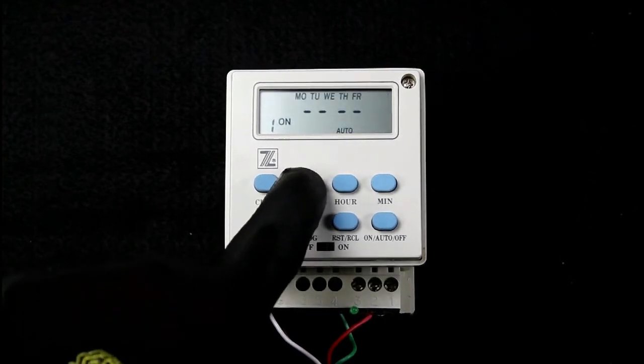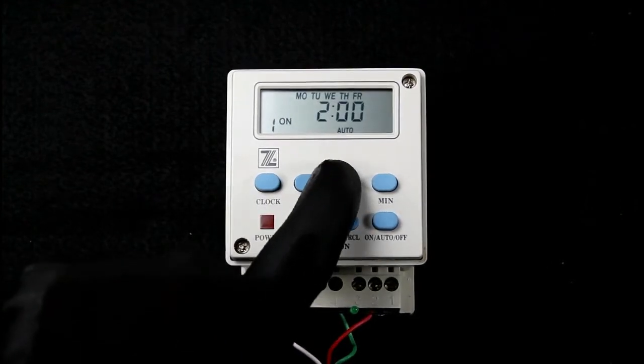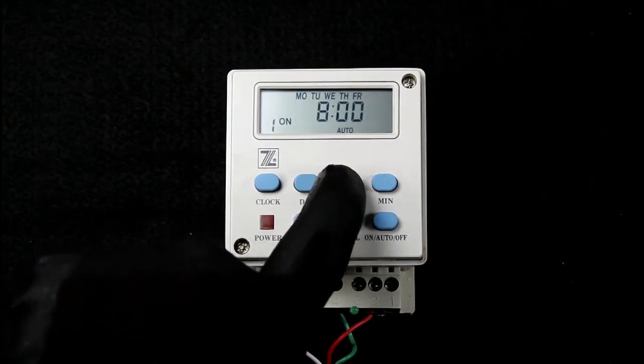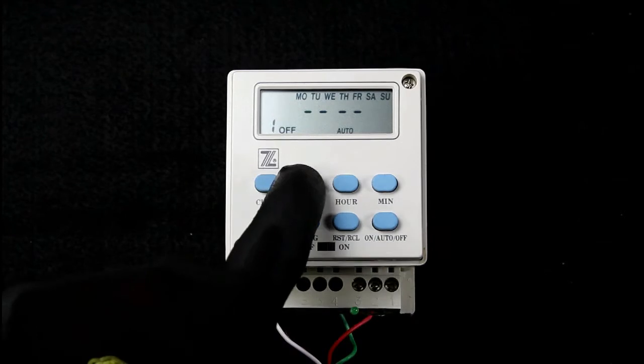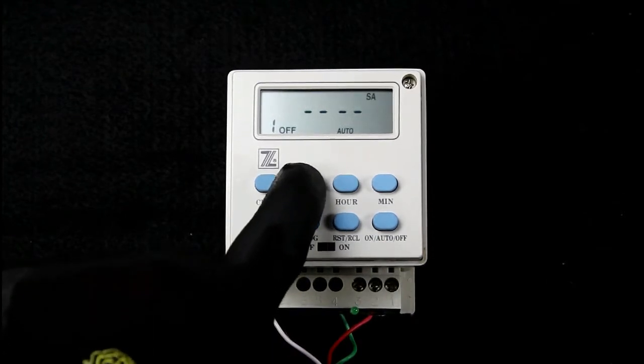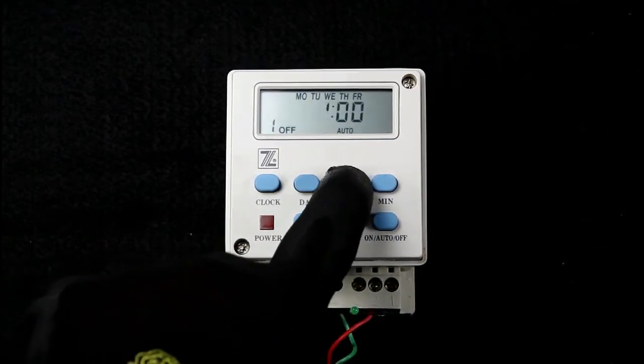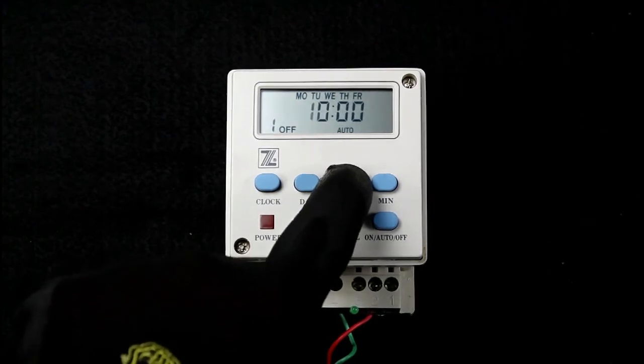Now we'll change the weekdays first, Monday through Friday. Next, the time to turn on the timer, 8 a.m. Next, the time to turn off the relay, Monday through Friday. We'll change this to 1700 hours, or 5 p.m., and press program.